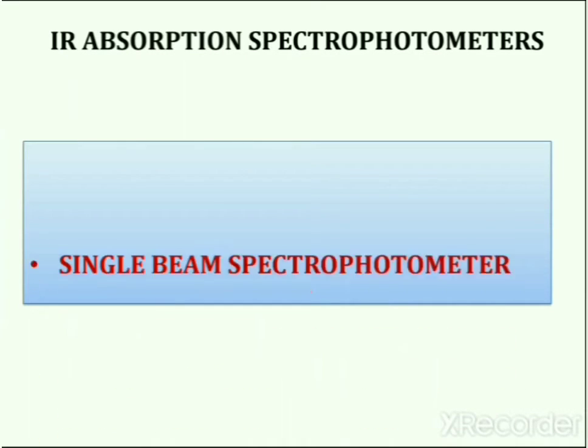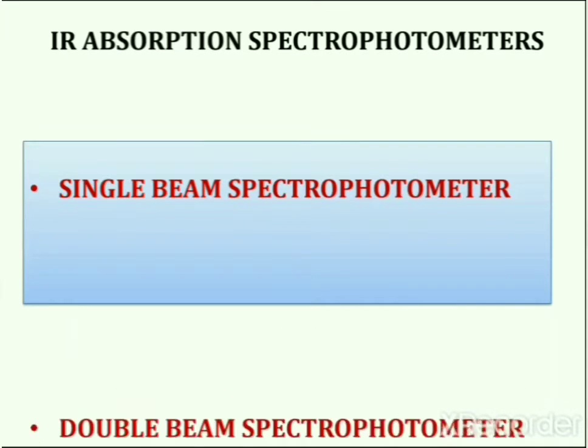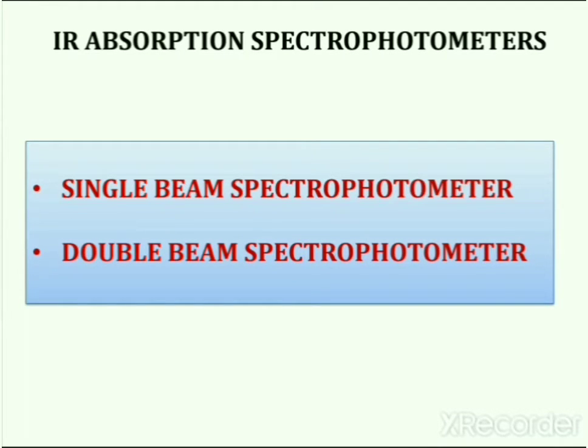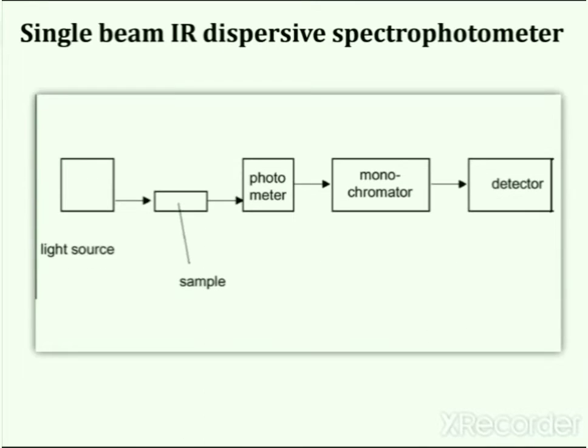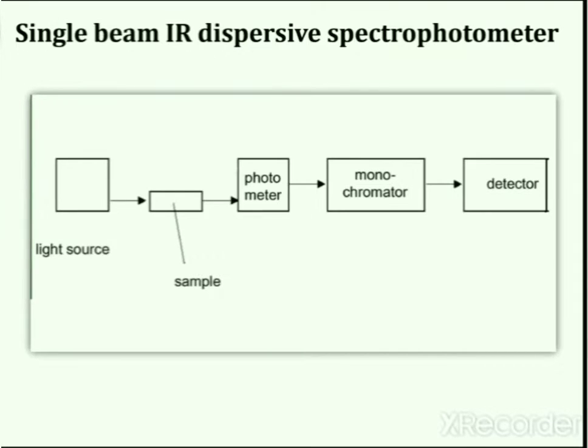There are two types of spectrophotometers in IR spectroscopy: single beam spectrophotometer and double beam spectrophotometer. A single beam spectrophotometer uses a single beam of light which can pass through one solution at a time. In a double beam instrument, a single beam of light splits into two separate beams — one passes through the sample and another passes through the reference. Modern dispersive IR spectrophotometers are invariably double beam instruments, but many allow single beam operation via a front panel switch.